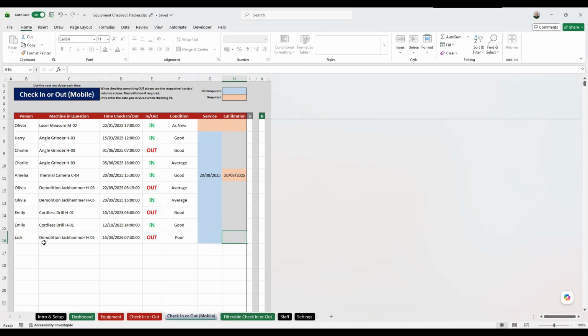While you have the machine in your possession, you can service or calibrate it as needed. When you return it, it'll change color again—red if required—and you can pop in the date when you actually did the service or calibration, and it will clear it back out. So instead of giving you dates, it just changes colors. The reason I've done it like this is just to make the whole screen narrower.